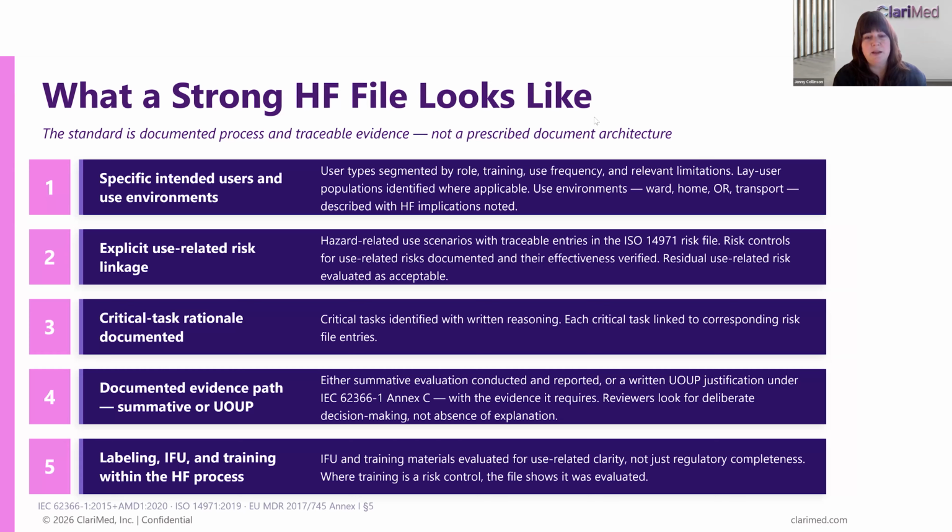So you need to be considering 14971 in the development of your usability engineering file, and it shouldn't be a standalone document because that will generate questions. And I think the reviewers are really familiar with 14971 and less familiar with 62366. So if we can talk about it in those terms, then it's more likely to be acceptable.